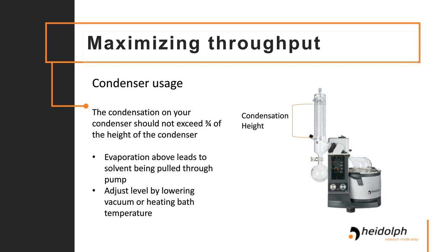If you see that you're evaporating past the 3/4 mark on your condenser, you can increase your pressure a little bit so that it's not evaporating as strongly. Or if you're a bit below that 3/4 point, you can pull your vacuum down a little bit to bring it back up to that level. Keeping it around there will really maximize how much you can evaporate off at a time.